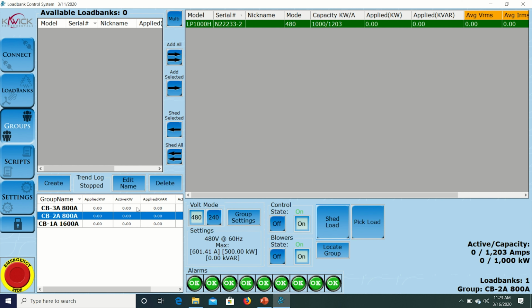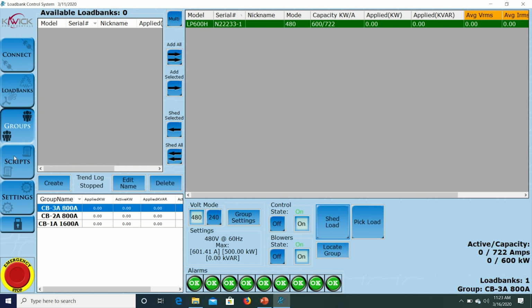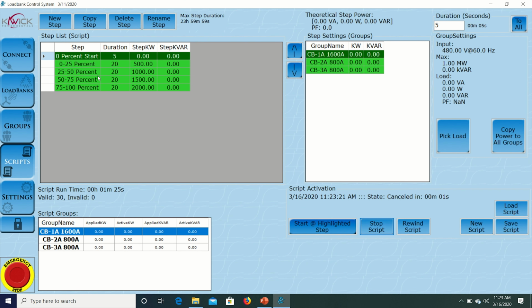When you go to restart your test, the step that you start on will start from the beginning of that step. So say you were in the middle of a 2-hour burn at a specific load and stopped an hour into it. It doesn't pause and restart with an hour left to go. It will start again at the beginning of the duration of that step. You can easily adjust the duration of the step and then continue if that is what is desired. We have successfully run through our script.